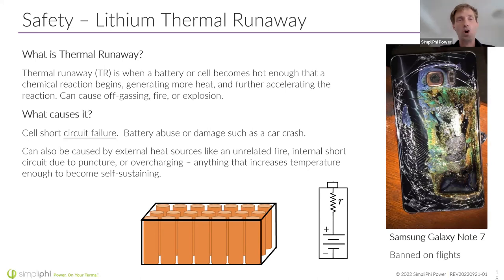The point is, the cobalt-based batteries off-gas and release the energy very quickly. And it's essentially a chain reaction in which one cell causes the next cell, et cetera, to react and off gas and burn. And that's a fire that's very difficult to put out because the fuel is there with the fire, as well as those cobalt oxides, the oxygen is there inside the cell as well. So those are difficult fires to put out.